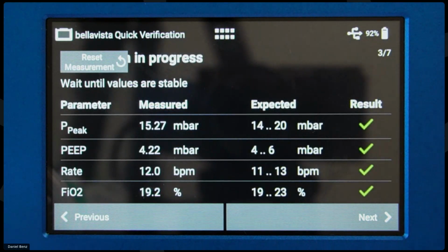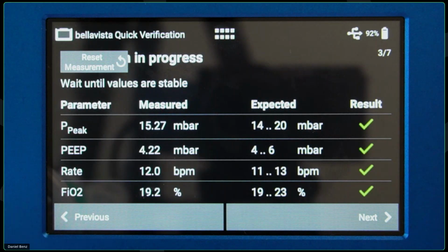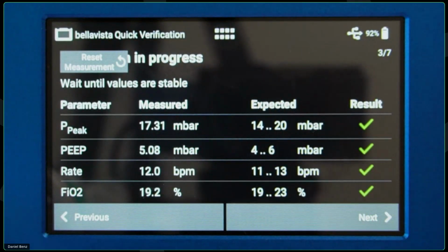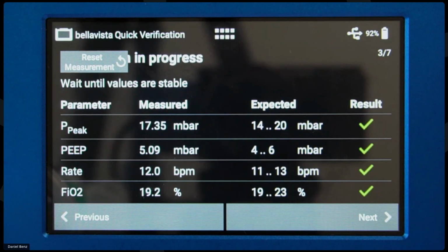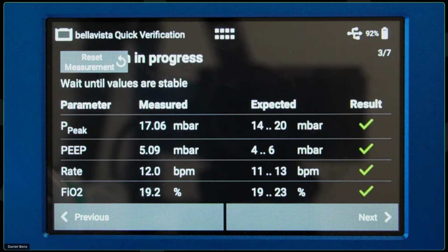And then when it comes to take measurements, again, this is exactly what the ventilator manufacturer specified and wants you to test. You don't have to go and find the corresponding measurements. It's all there, as you can see in a table. It shows you the measured value, and it also shows you the expected range, as well as a pass-fail result right on the screen. Some ventilators, even in their testing procedures, you even need to calculate the expected range because it's based on a measurement.